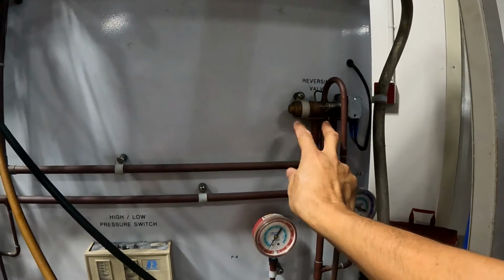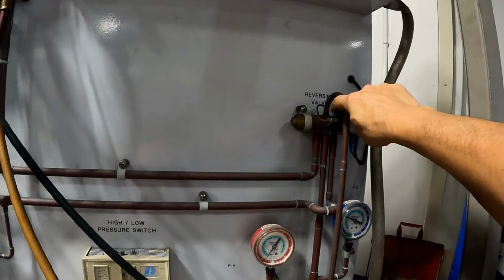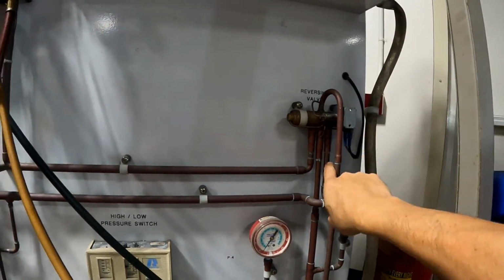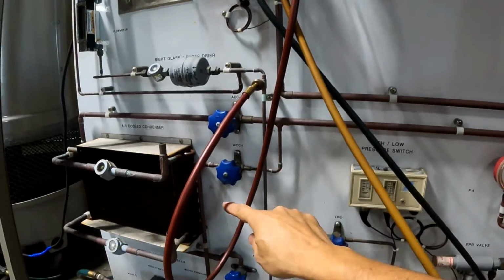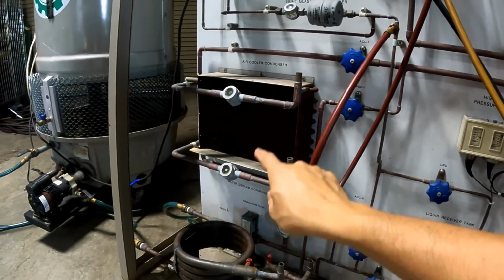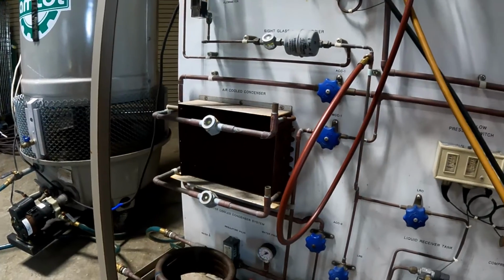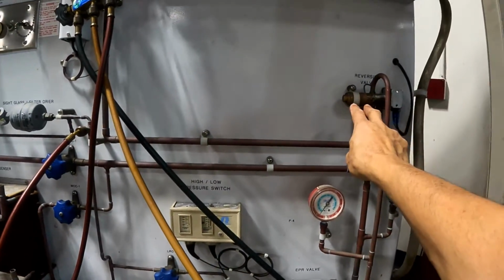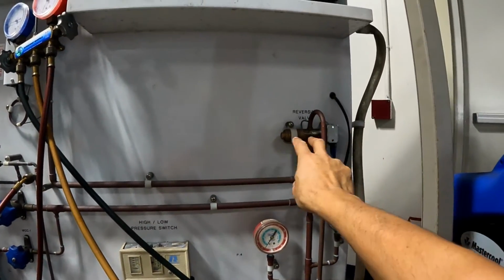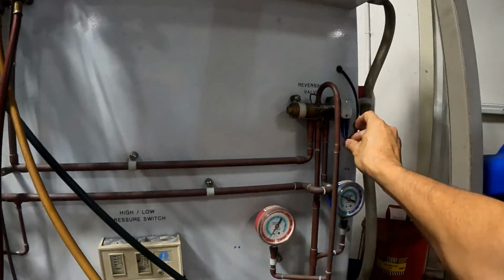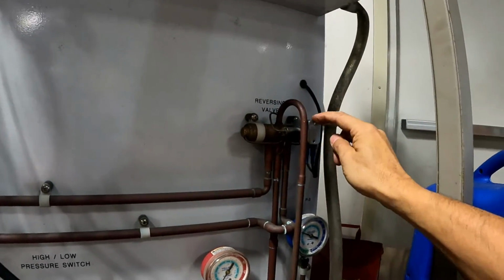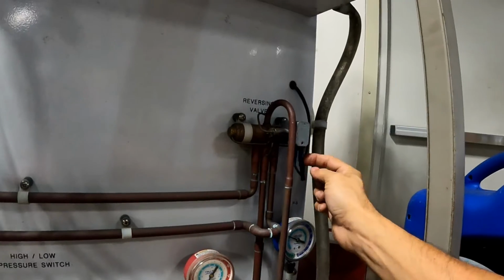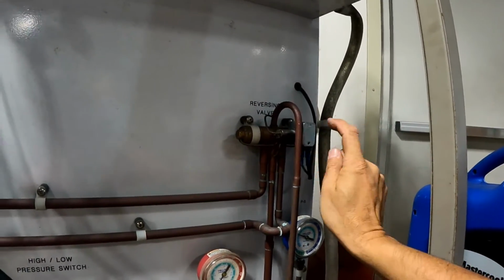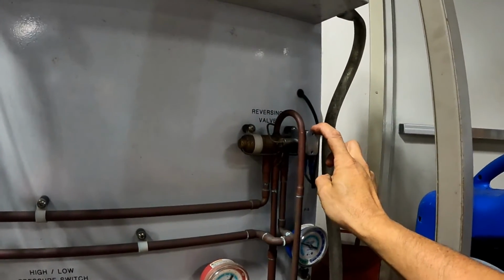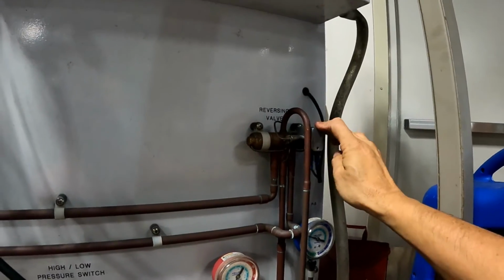If the metal is located in this portion, the high pressure refrigerant goes over there and goes into the condensers and works in the cooling mode. Yes, the secret is where the metal is located internally.